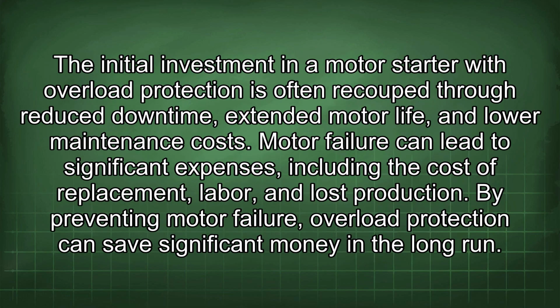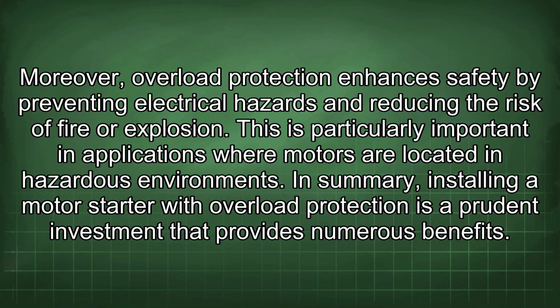The initial investment in a motor starter with overload protection is often recouped through reduced downtime, extended motor life, and lower maintenance costs. Motor failure can lead to significant expenses, including the cost of replacement, labor, and lost production. By preventing motor failure, overload protection can save significant money in the long run. Moreover, overload protection enhances safety by preventing electrical hazards and reducing the risk of fire or explosion. This is particularly important in applications where motors are located in hazardous environments.